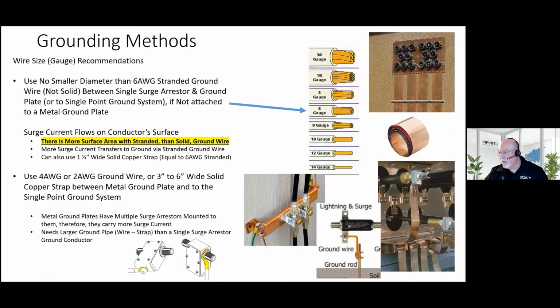Okay, and now the cable we recommend. Let's say you're hanging this RF coaxial surge arrestor, and it's not mounted to a ground plate. It's just hanging out in the air, and it's weatherized properly, but it still needs a dedicated ground path. So you use a ring terminal. So what size cable do you use? You use a 6-gauge stranded. Lightning surge current travels on the surface of the conductor, and you get more surface area with a stranded wire than a solid wire. So we always recommend a number 6 stranded, not solid ground wire.